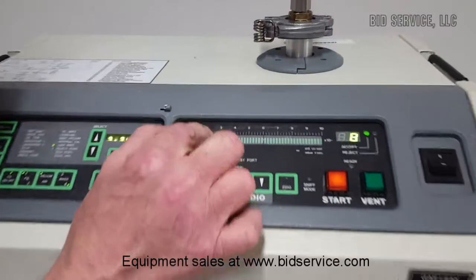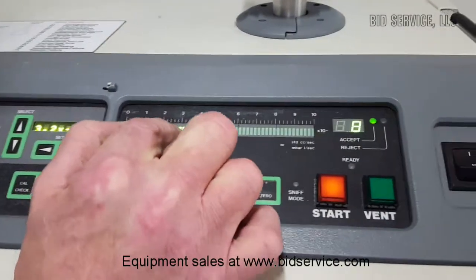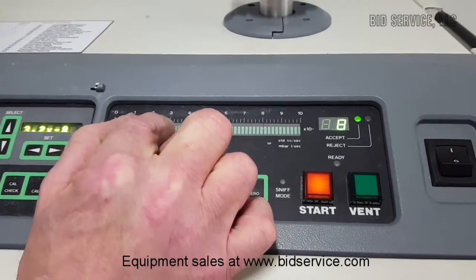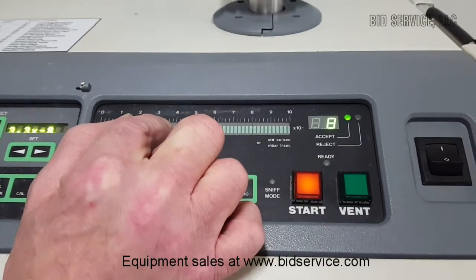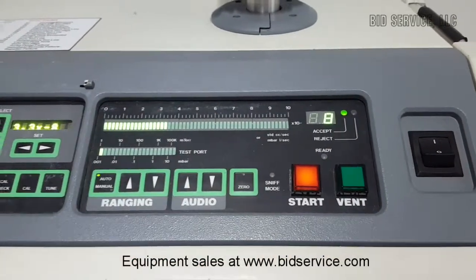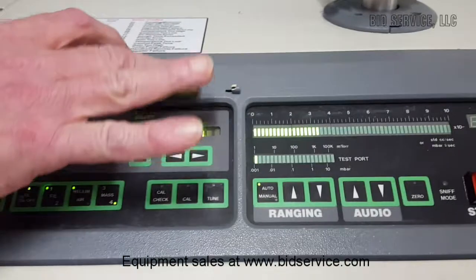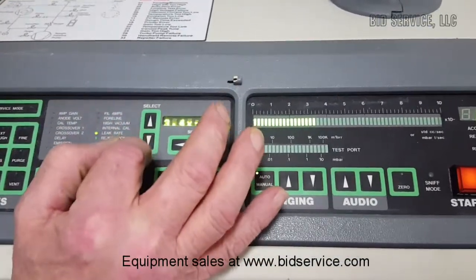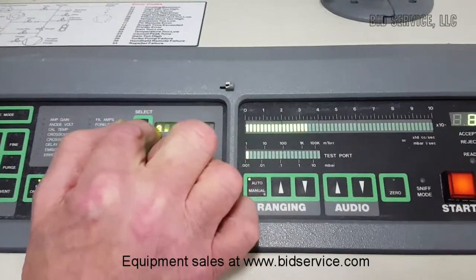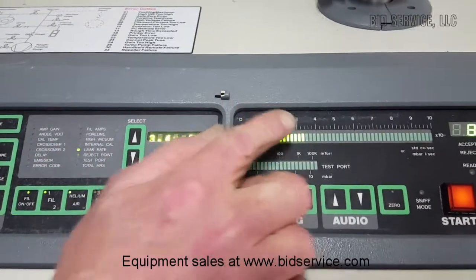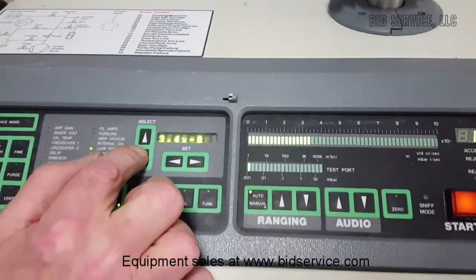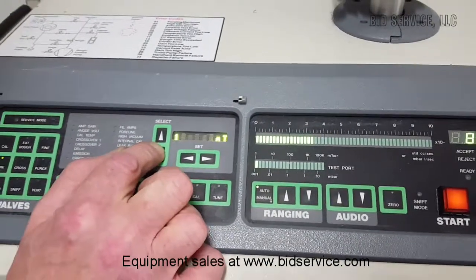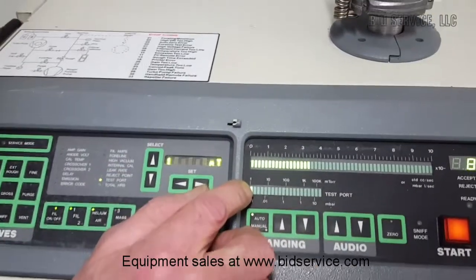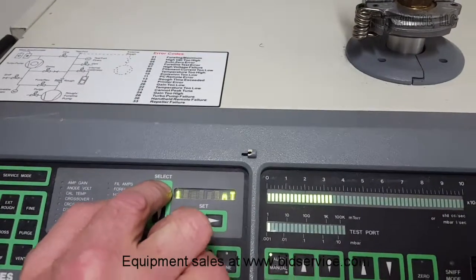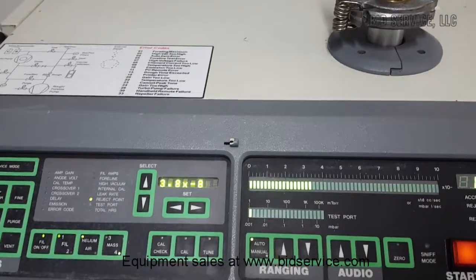And we have a reading of between, oh, excellent, 3.2 and 3.3. This is another nice feature over here. Even though this is in the service mode, you can select these different indicators here. For example, this will also read out the leak rate that we are at. It'll also let you know that we're all the way down on the test port. But this one's important. This is your reject point.